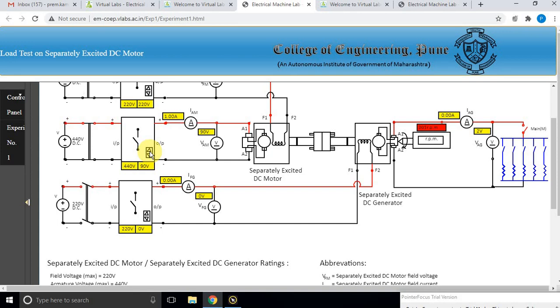Bring the armature voltage to nearly 435 volts. You will see the variation of that voltage as well as the speed of the machine. Adjust until the speed reaches approximately 1500 RPM, which is close to the rated speed of the motor.